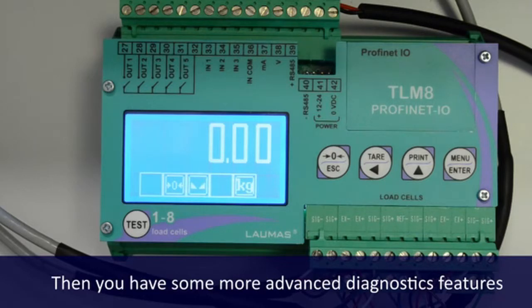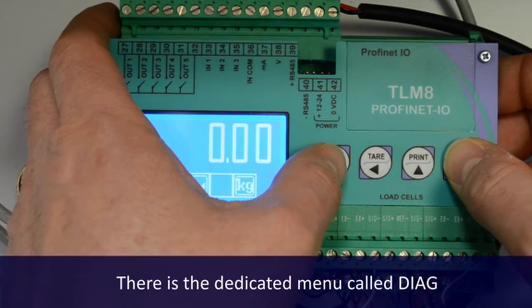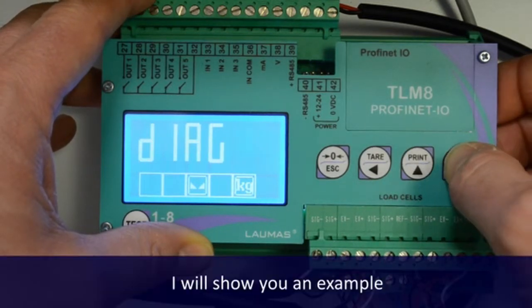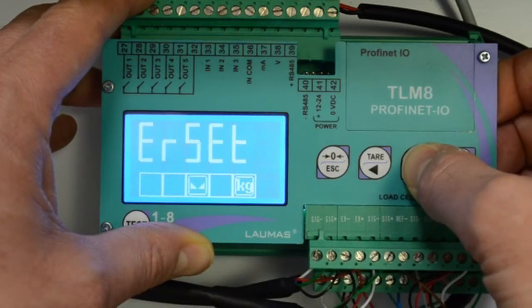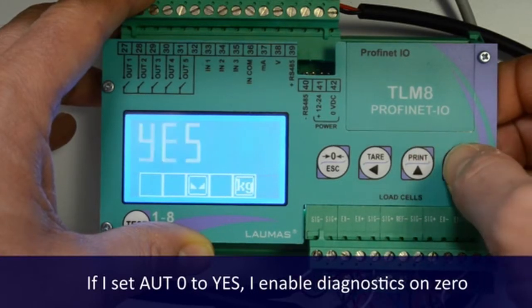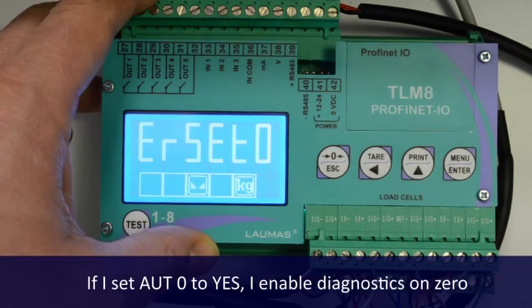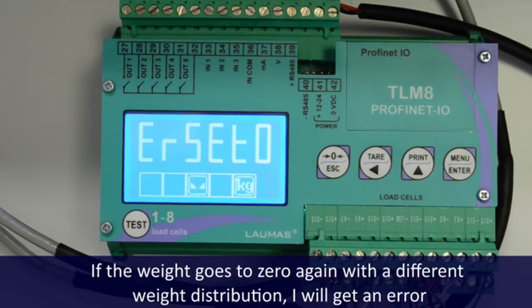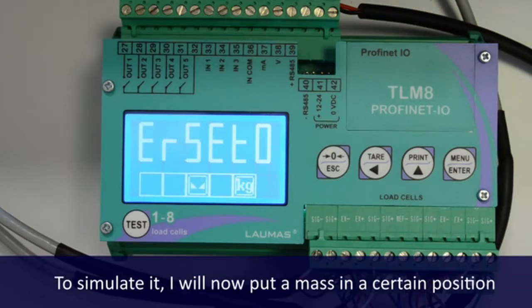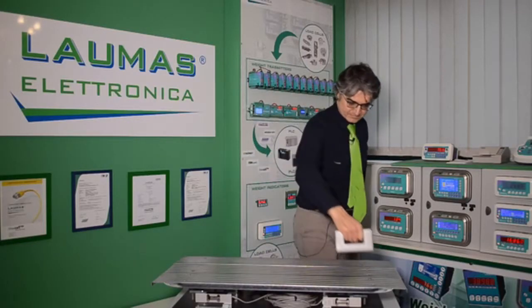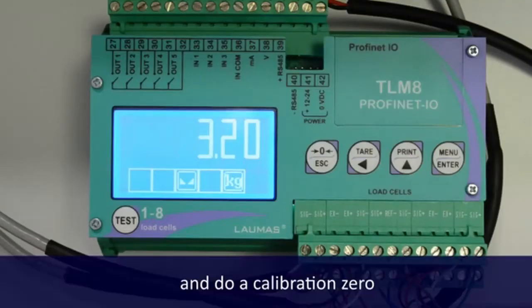Then you have some more advanced diagnostic features. There is a dedicated menu called Diag. Here you are. I will show you an example. If I set auto 0 to yes, I enable diagnostic on 0. So when I set the weight to 0, the system stores the weight distribution. If the weight goes to 0 again with a different weight distribution, I will get an error. To simulate it, I will now put a mass in a certain position. And do a calibration 0.